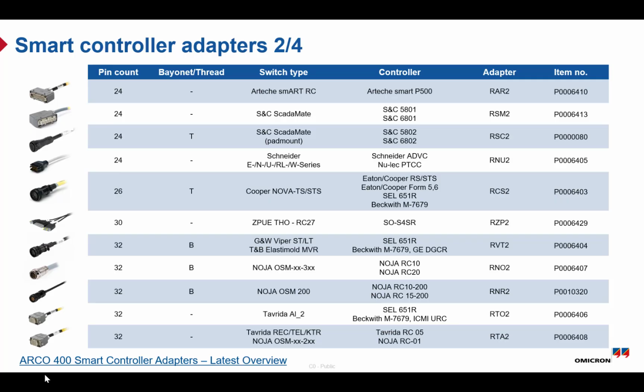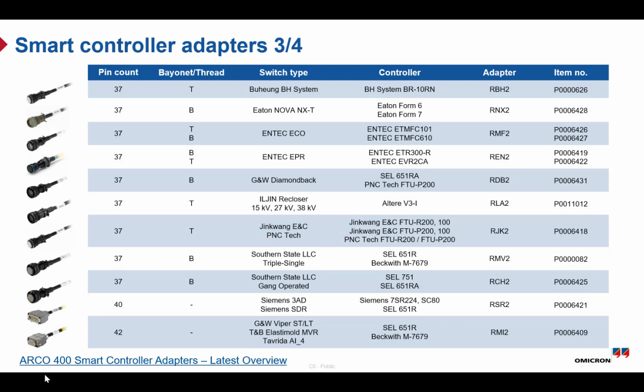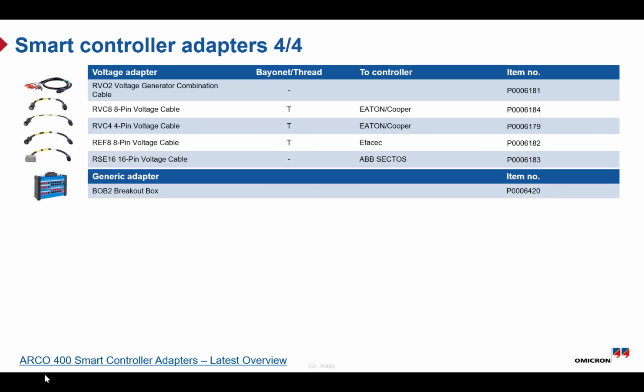So in summary, there is a wide range of adapters available to cover different applications. For the full list, you can always check the Omicron website or reach out to us. Here are different types of smart adapters available for various controllers of the recloser manufacturers such as Eaton, ENTEC, Jinkwang, SEL, and Siemens. To identify the adapter that best matches the pin-out configuration of your recloser, you simply need to check two things: the recloser switch type and the controller relay type. Once you know these details, you can proceed with ordering the correct adapter from us using the corresponding item numbers. However, to ensure you select the right adapters, you are welcome to share this information with us and we will be happy to assist.